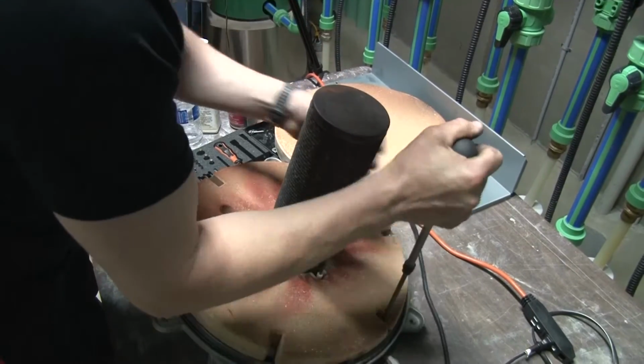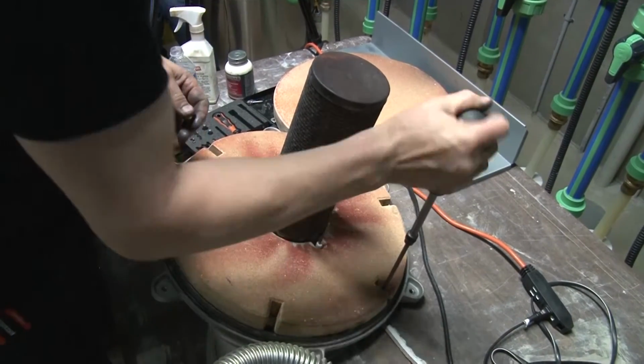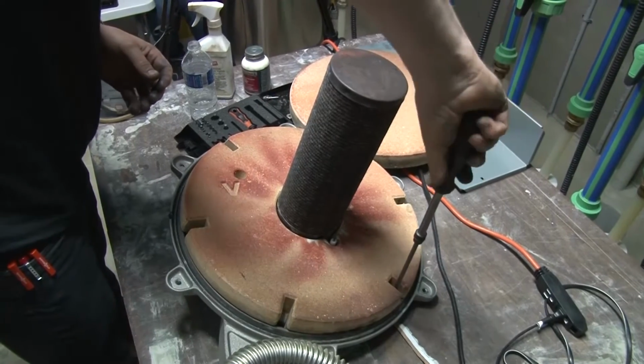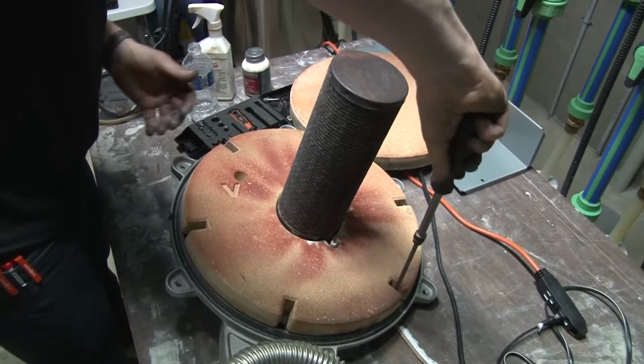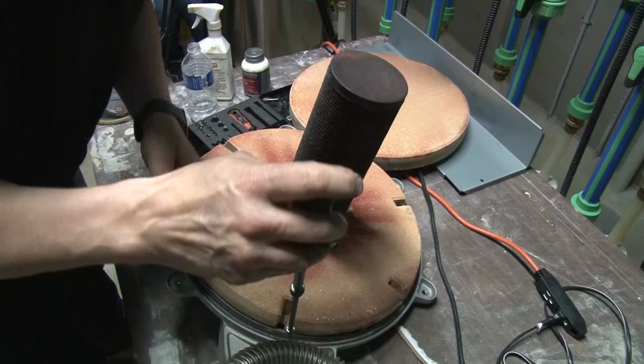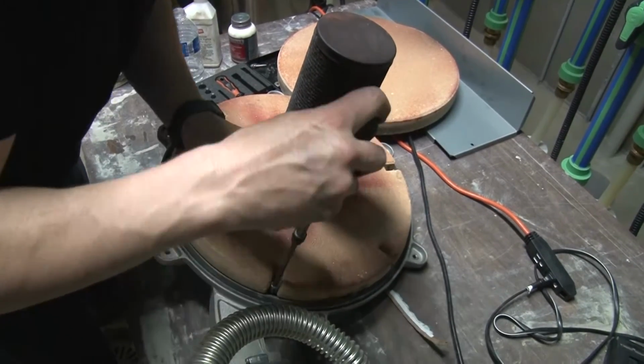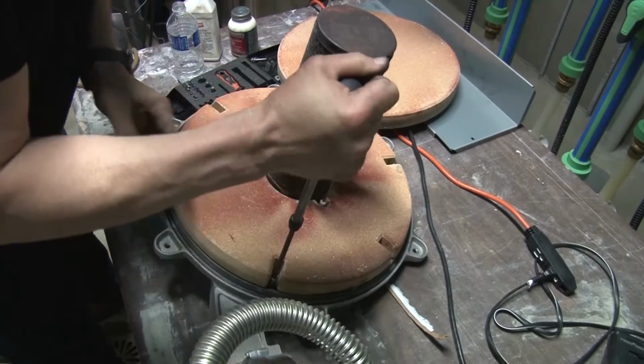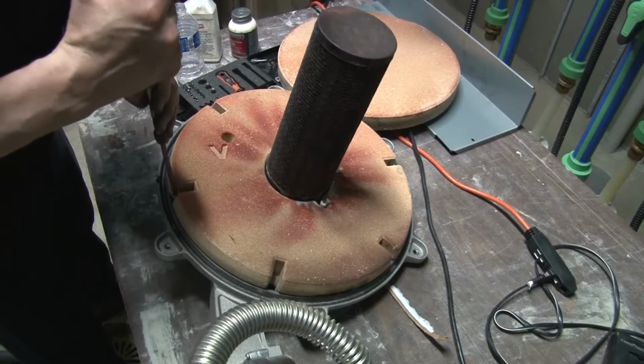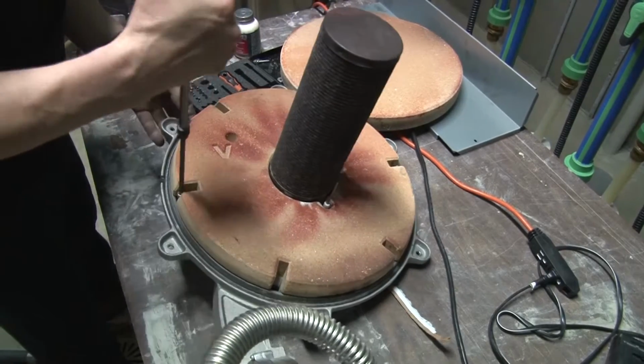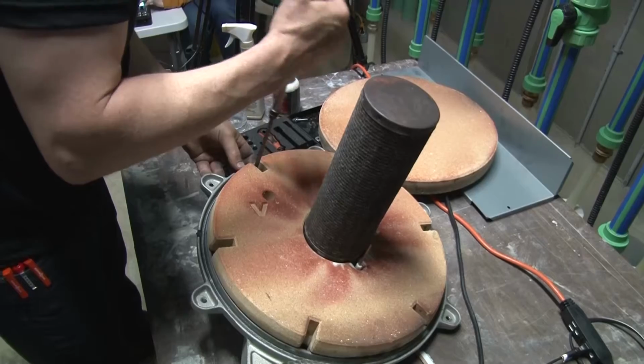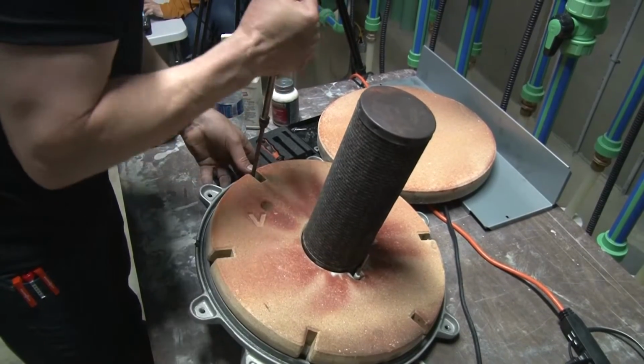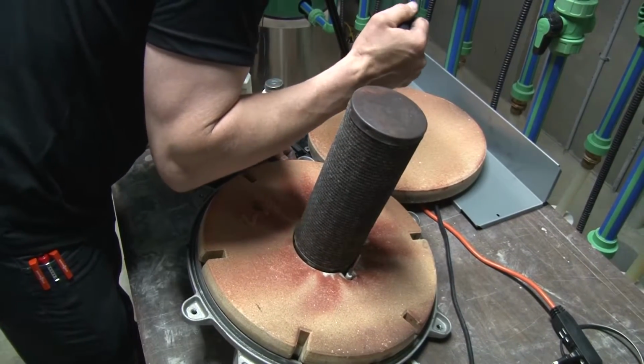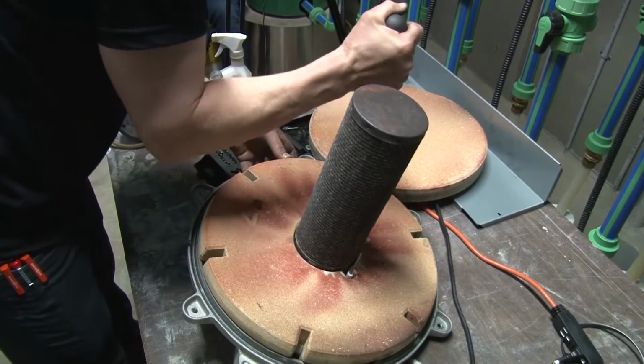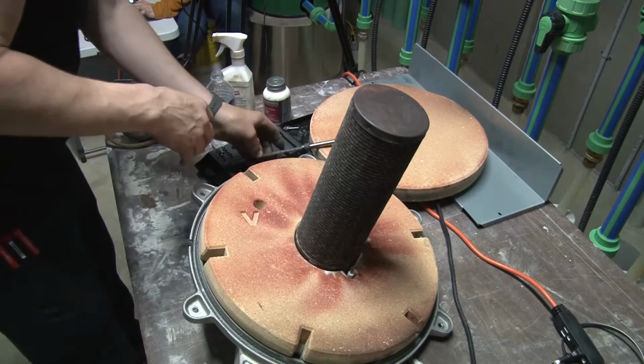And if I was to grab the information in the service manual, and these were not new electrodes, and I want to check their gaps and stuff, make sure that they were good to go. I believe in the manual it's going to say something along the lines of on the ignition electrode, 6 millimeters, 5 millimeters, and 4 millimeters. If you've got Allen keys, so let me see. I got some Allen keys sitting here.